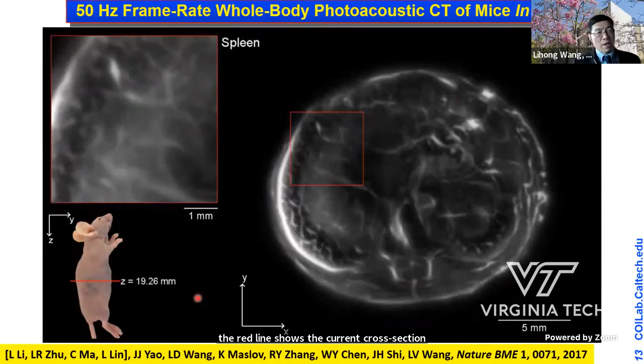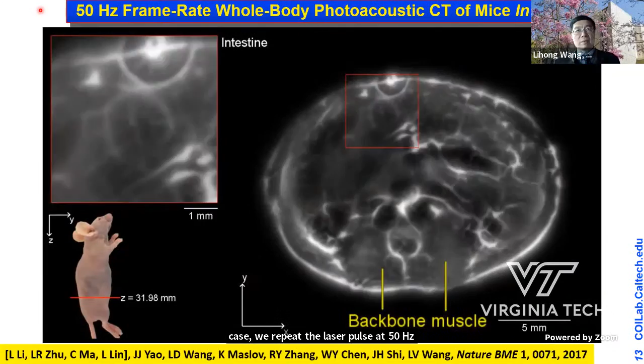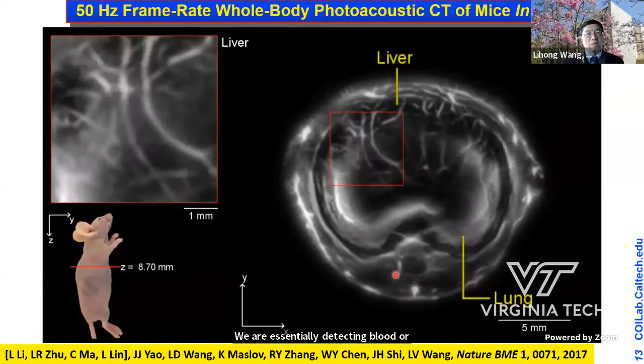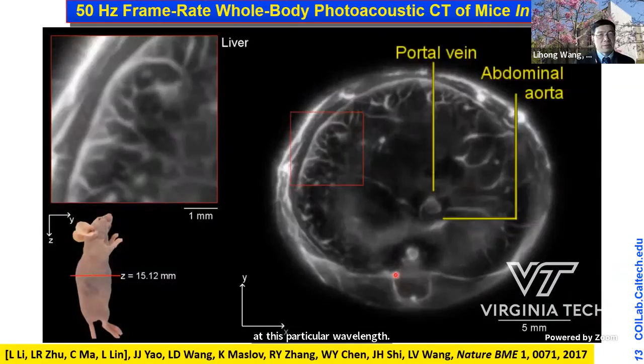Again, a single shot takes only tens of microseconds to acquire, and then we repeat our laser pulse. For this particular case, we repeat the laser pulse at 50 hertz, so you get 50 frames of images per second. Without injecting any contrast agents, we can see the structures in the body. Here, we're essentially detecting blood or hemoglobin as our contrast mechanism at this particular wavelength. You can tune our laser wavelength, of course, to image some other absorbers in the body.